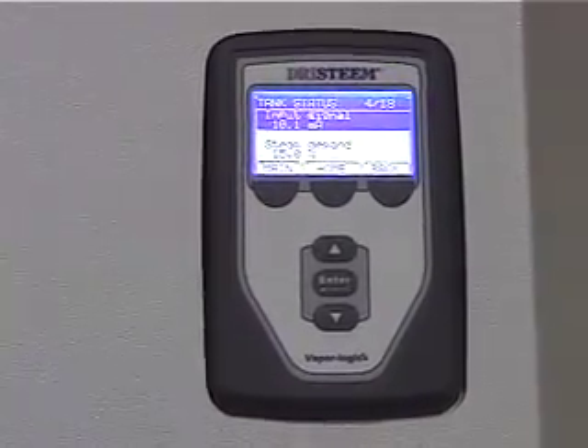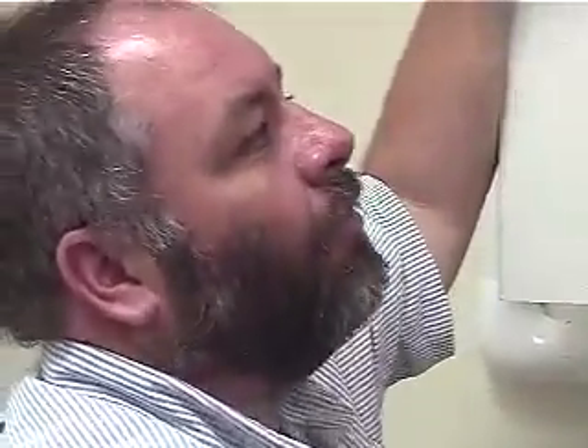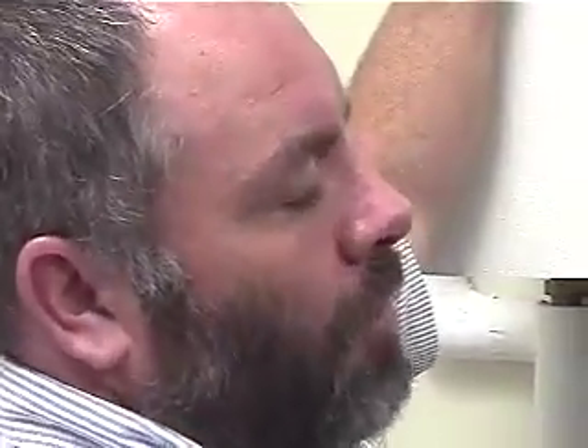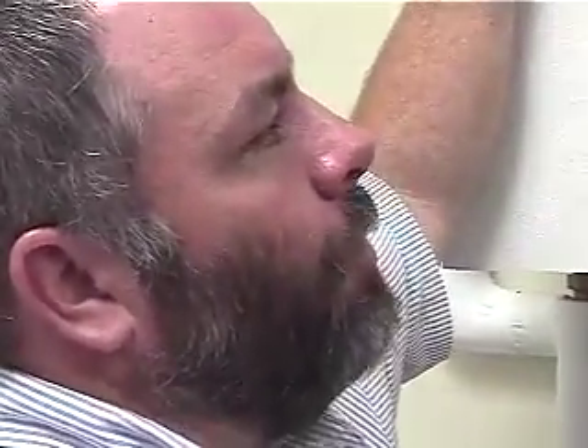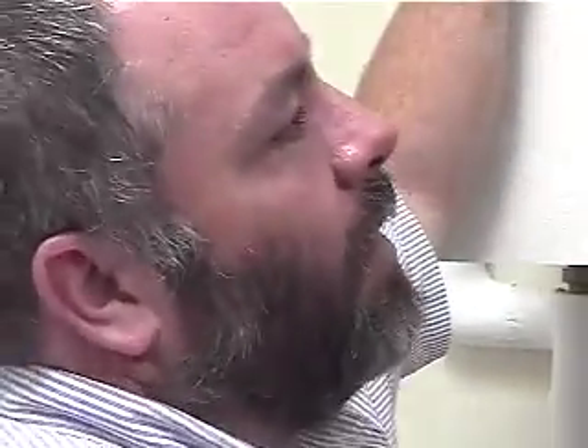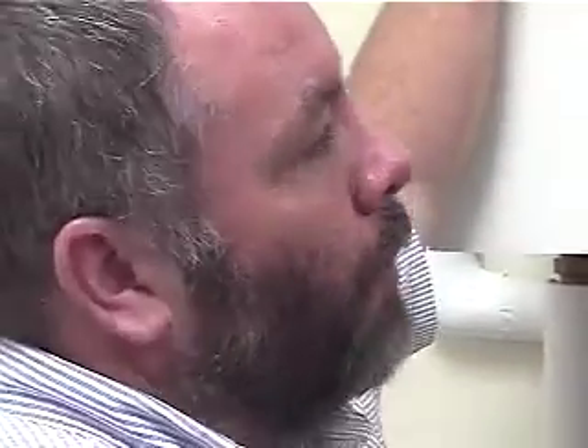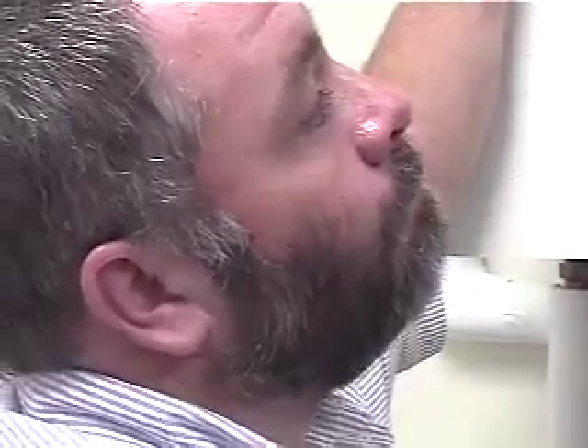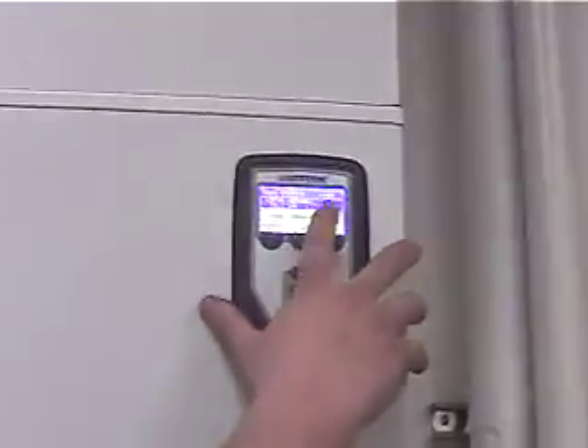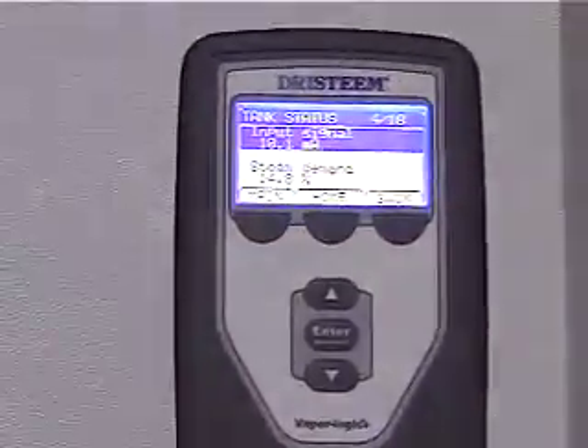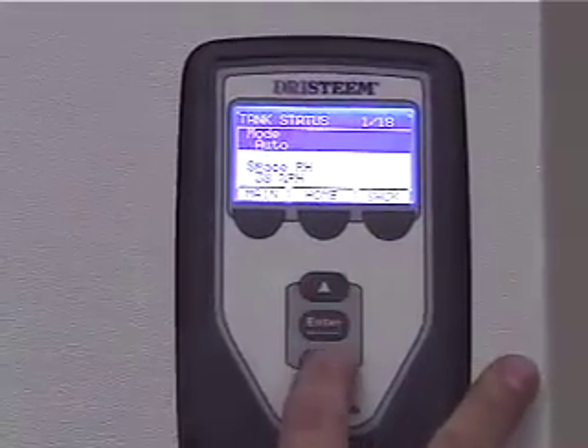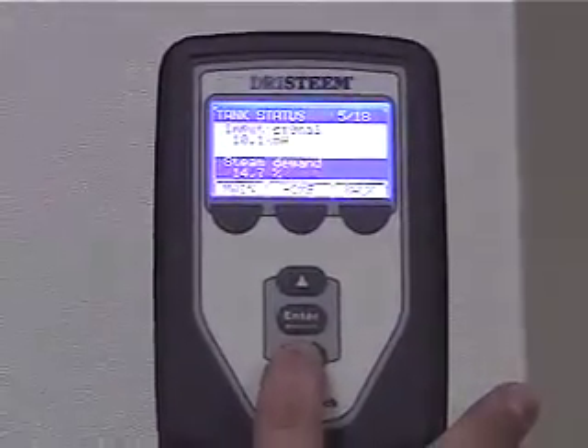A lot of times we get into these and they try to control your humidity to 1/10%. And so these things are on and off and on and off. It's just like controlling your air temperature in a room to a tenth of a degree. It's not going to happen. You'll get 3 or 4 degrees. Same thing here. You're going to have a 3 or 4 percent swing in a room, period. Up here at the top, it tells you you're on the 4th item of 18, so you know how many items you can go through.